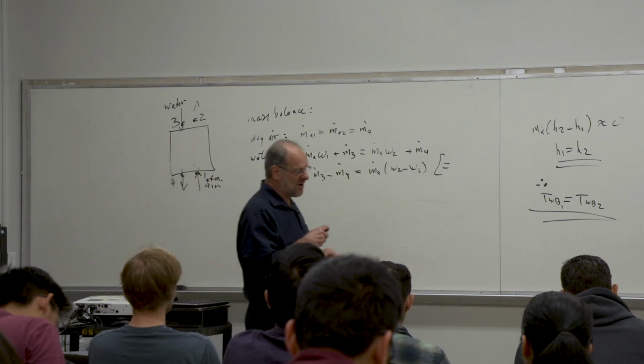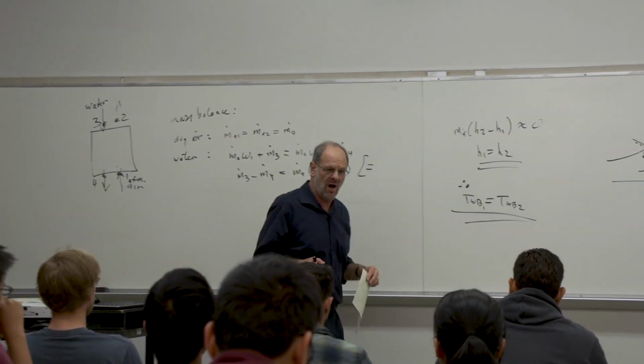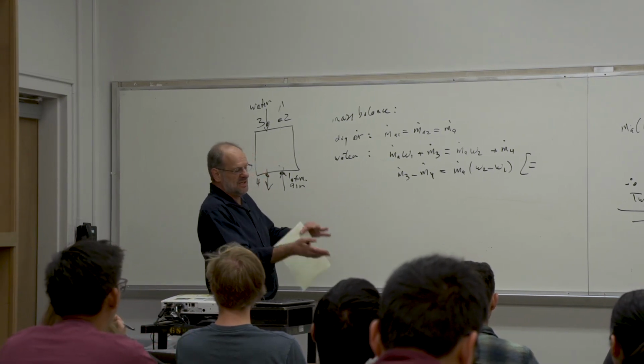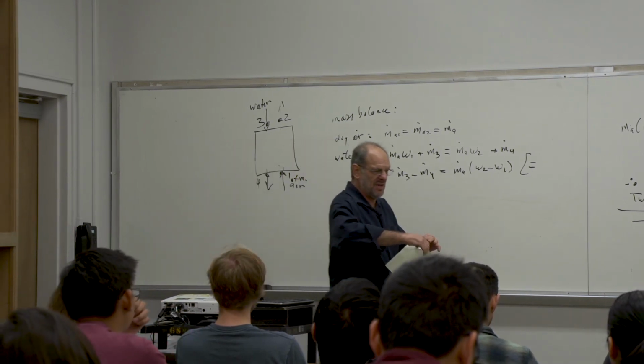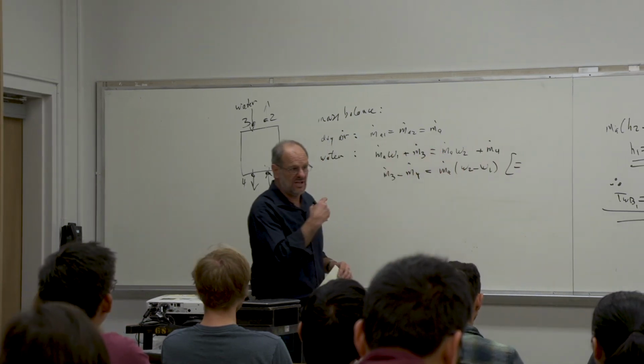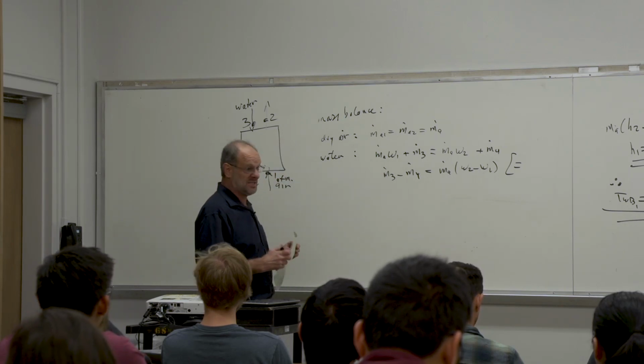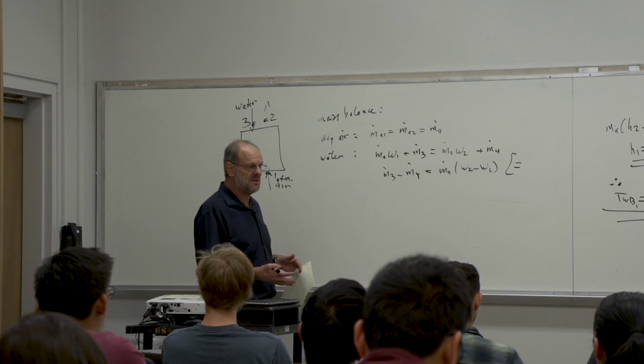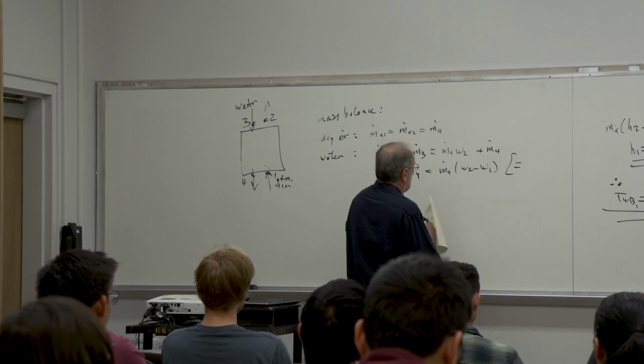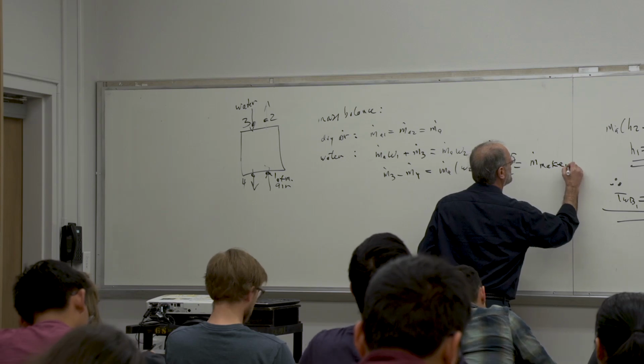Now, I mentioned just a few minutes ago that in a typical large cooling tower, you could lose 1 million gallons a day of water. You need to provide a makeup water supply to that. You know, it's not like a swamp cooler where you just want to leave the valve open and maybe have like a little float valve like in a toilet or something, just so you always have water in the swamp cooler. Here, you need to continually provide makeup water, and 1 million gallons a day of water is a lot of water. You need a dedicated system. That system has to be reliable. So this is equal to the mass flow rate of what we'll just call the makeup water.